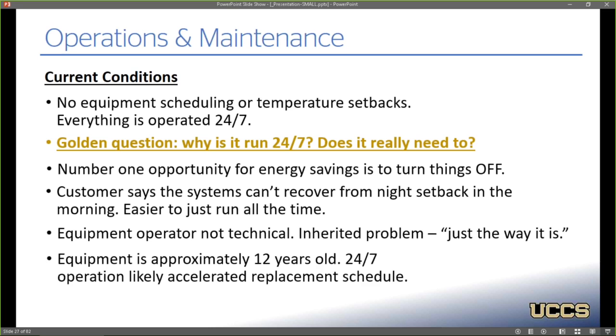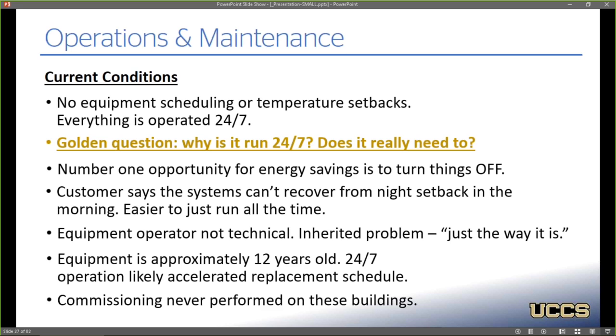This equipment is approximately 12 years old, and normally I wouldn't recommend full mechanical replacement after 12 years, but the 24/7 operation for who knows how many years has probably accelerated that replacement schedule. And the last thing to note is that commissioning was never performed on these buildings. At the time, it was not an energy code requirement as it is now, so it's not terribly surprising.